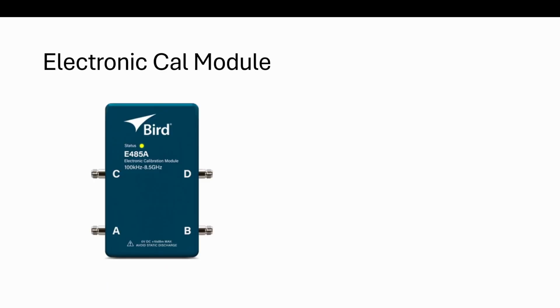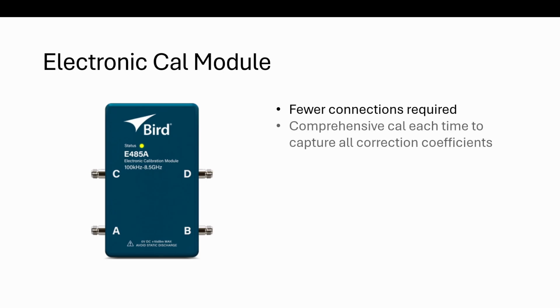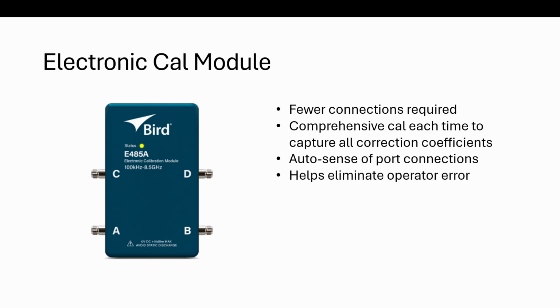Use of an electronic calibration module will help limit the number of connections made since the device switching is integrated within the hardware. This reduces both time spent during the procedure and preserves your connectors. Because you can move faster, there is no need to skip steps, and you can achieve a comprehensive calibration every time. The module hardware and software promote auto-sensing between the VNA ports and those on the module itself. This practically eliminates connection mistakes that might be made by an operator.